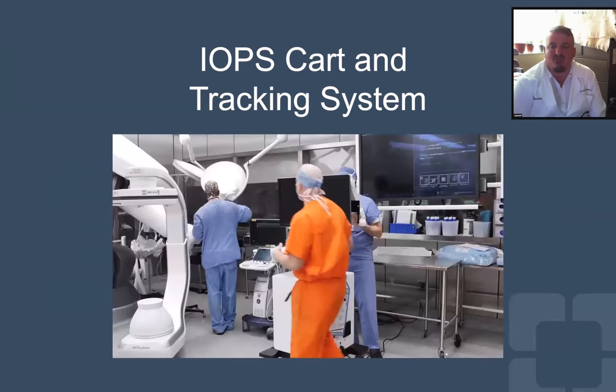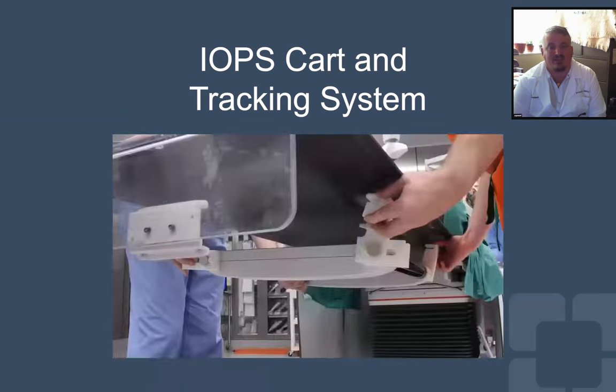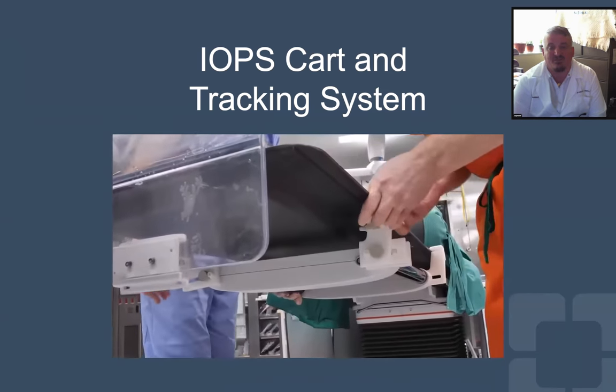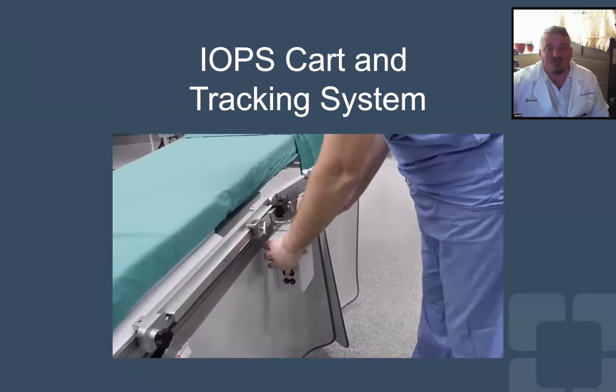Centerline Biomedical is a company that spun out of Cleveland Clinic with a system called IOPS. It is an adjunct to fluoroscopy that uses electromagnetic tracking. Here you can see it being set up alongside our Artis Pheno. There's a mobile cart and a tracking sensor attached to the table, making it very user-friendly and adaptable to other systems.